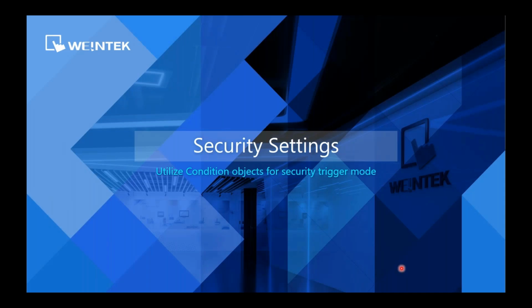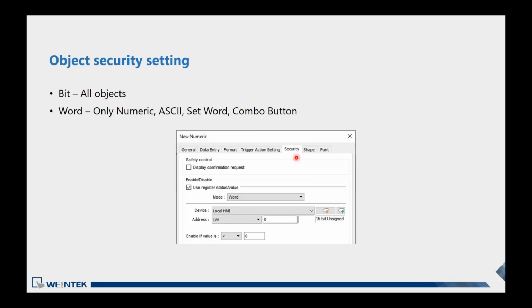Okay, so the next topic is trying to bring out the usage of the condition object and the word interlock, using the condition object and the security mode from all the objects. Regarding the security mode for each object, the most popular one is bit trigger mode, also known as bit interlock. And the security settings of some objects were added with the word judgment method due to customer requests, such as the numeric, ASCII, Set Word, and combo buttons.